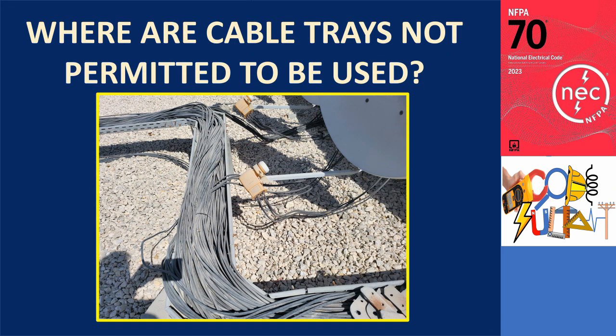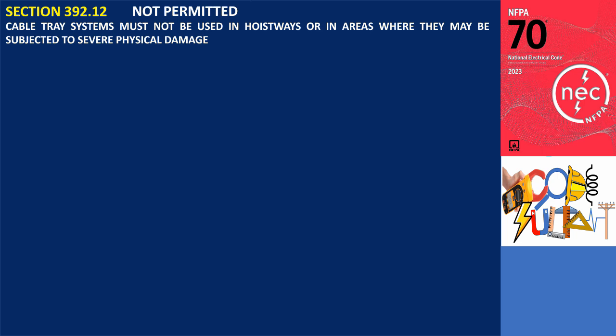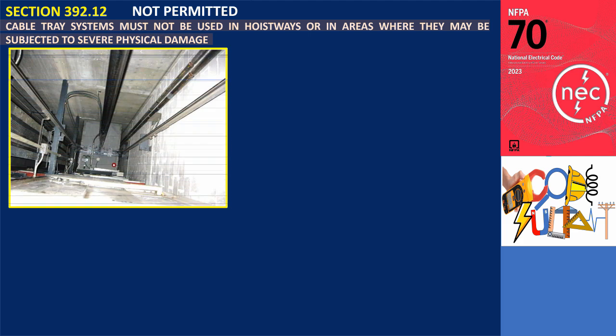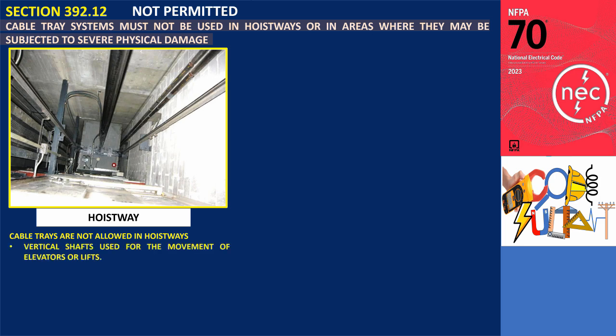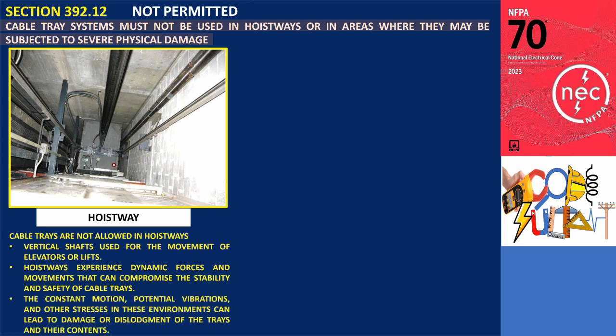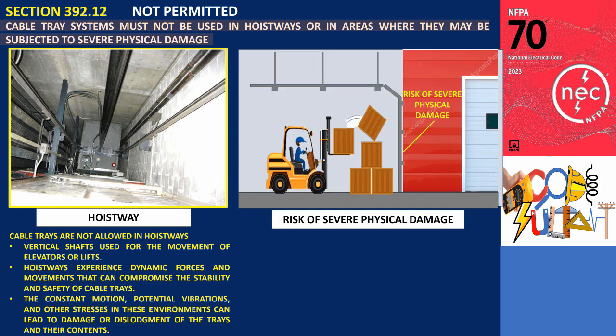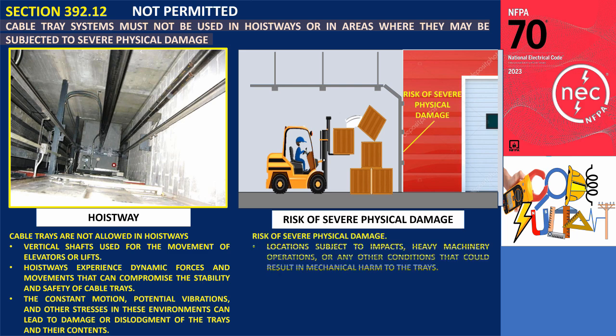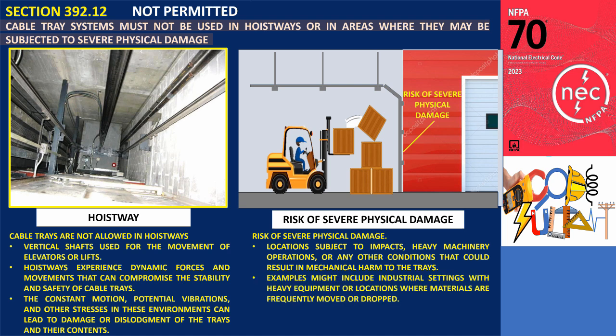Where are cable trays not permitted to be used? Section 392.12 Use Not Permitted. Cable tray systems must not be used in hoistways or in areas where they may be subjected to severe physical damage. Hoistways are vertical shafts used for the movement of elevators or lifts; the constant motion, vibrations, and other stresses in these environments can lead to damage or dislodgement of the trays and their contents. Additionally, cable trays should not be installed in locations subject to impacts, heavy machinery operations, or any other conditions that could result in mechanical harm, such as industrial settings where materials are frequently moved or dropped.